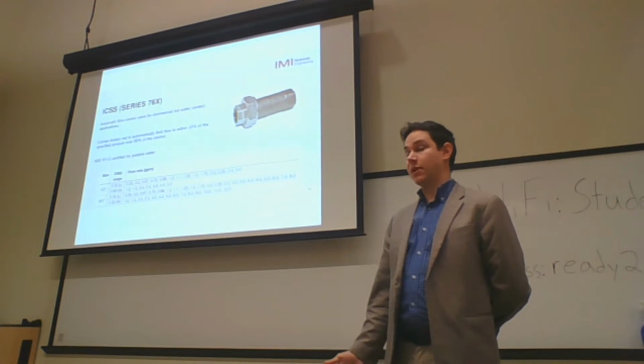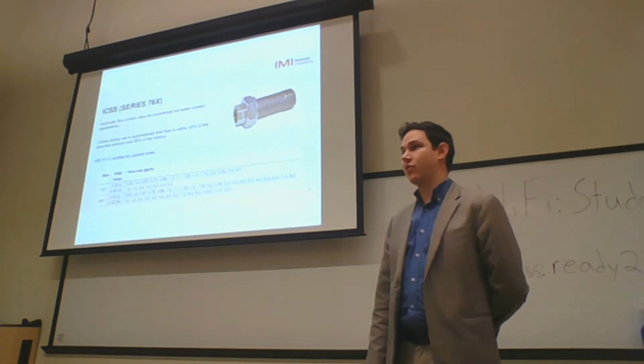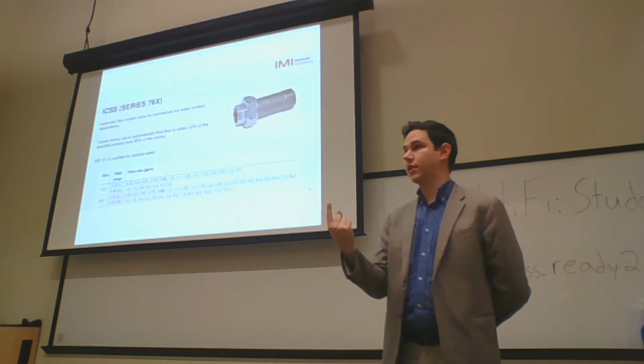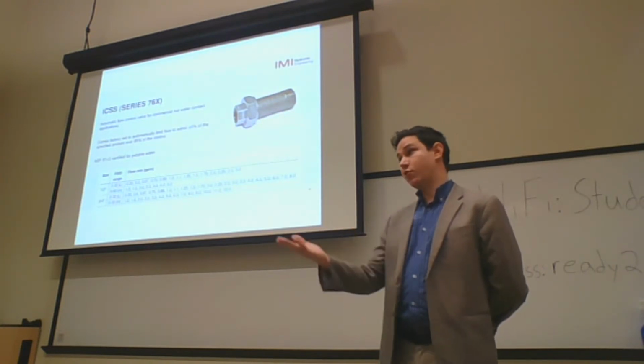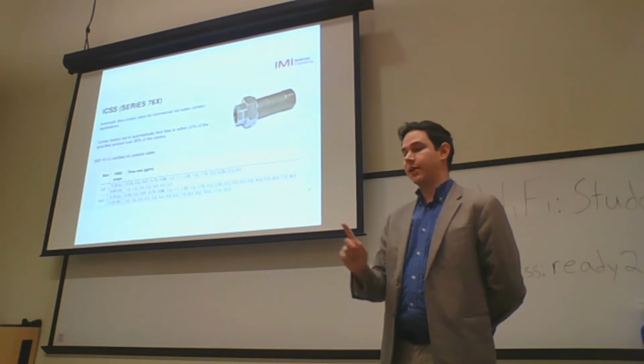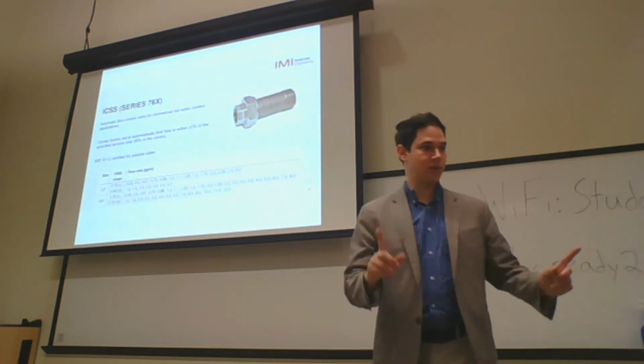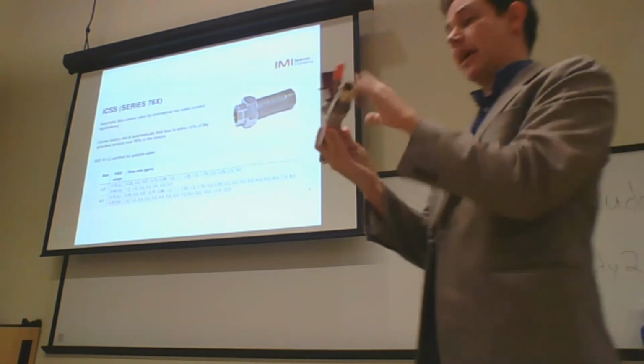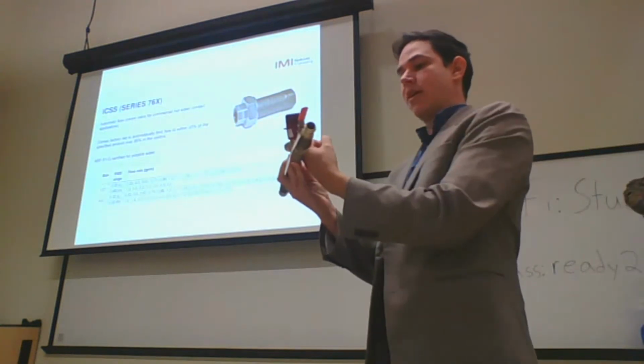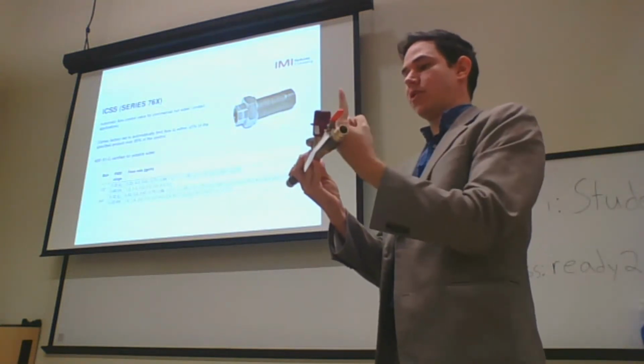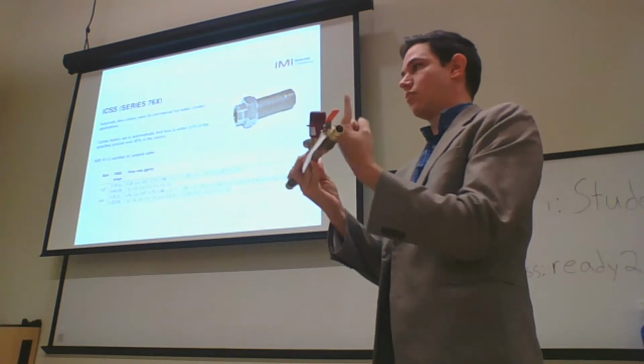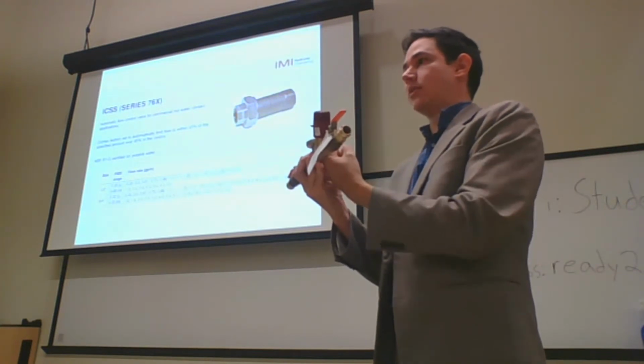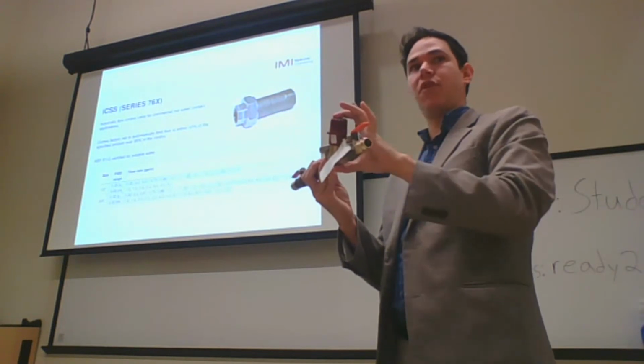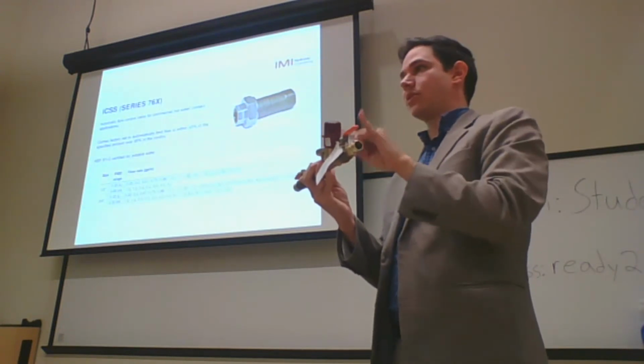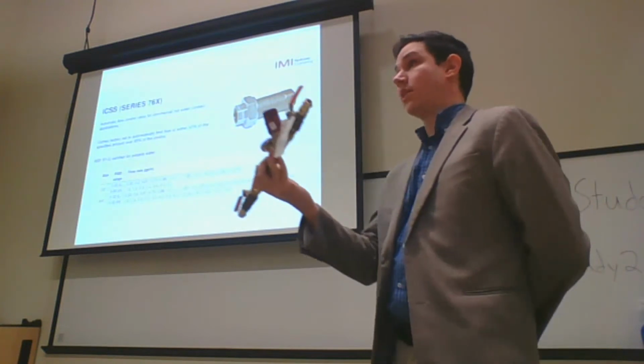You can measure with the ultrasonic flow meter, not at the valve. We have one of the valves with a PT port point. One other way, if you want to measure flow rate, would be getting the circuit with an extra PT port. For example, if you have this valve with one PT port at the body right here, you saw the option. If instead of a plain ball valve here, you install another PT port across the valve, you can measure the pressure drop. And on the submittal of this valve, you can find the CV.